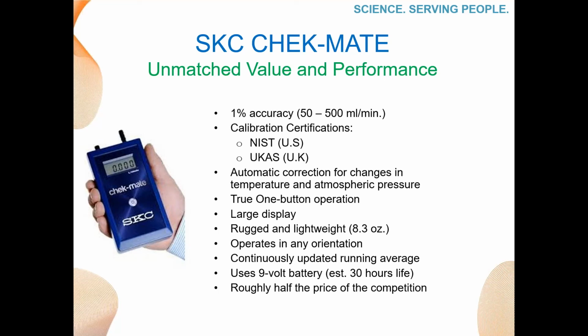We have a standard flow version with a range of 500 to 5,000 milliliters per minute. But obviously the low flow version, which is what you would use for the Pocket Pump Touch, is what I want to cover today. It has a range of 20 to 500 milliliters per minute with 1% accuracy in the range of 50 to 500 milliliters per minute. It has NIST and UKAS certifications. It is ready to use when you need it because it automatically corrects for changes in the environment with temperature and pressure. It has a true one-button operation and a very nice large display for the continuously updating running average.